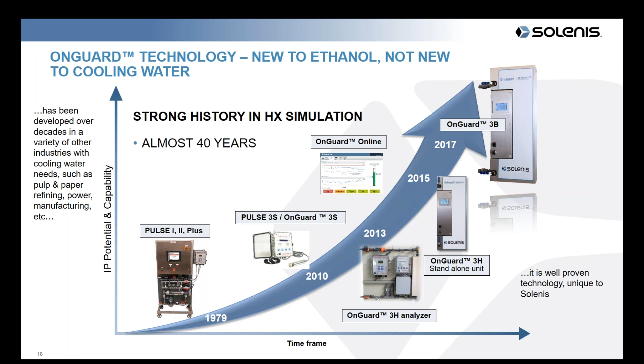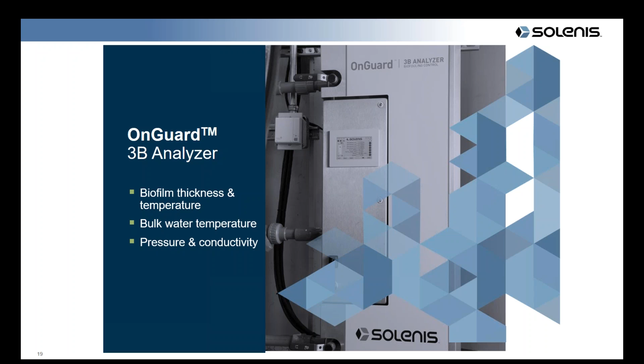We monitor the biofilm thickness and the difference in temperature across the heat transfer surface to come up with a true engineering fouling factor, and compare that to the bulk water temperature. We also monitor pressure and conductivity, because we have to account for the difference in the speed of sound as the water temperature changes, and the kinematic viscosity needs to be controlled, so we control the flow of the water as well.